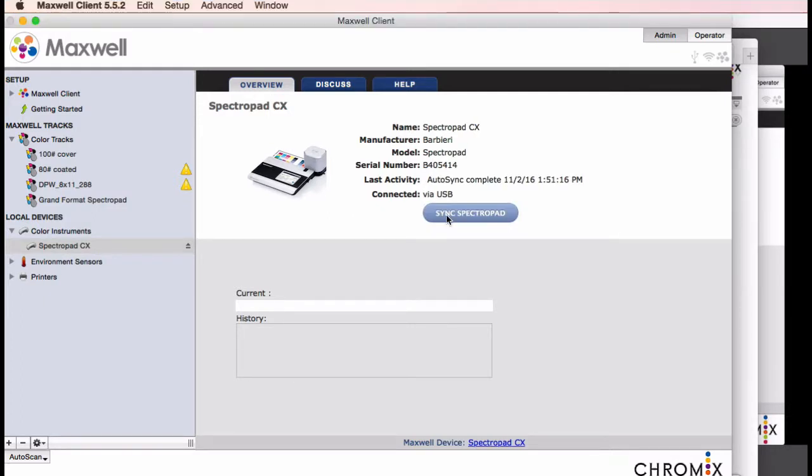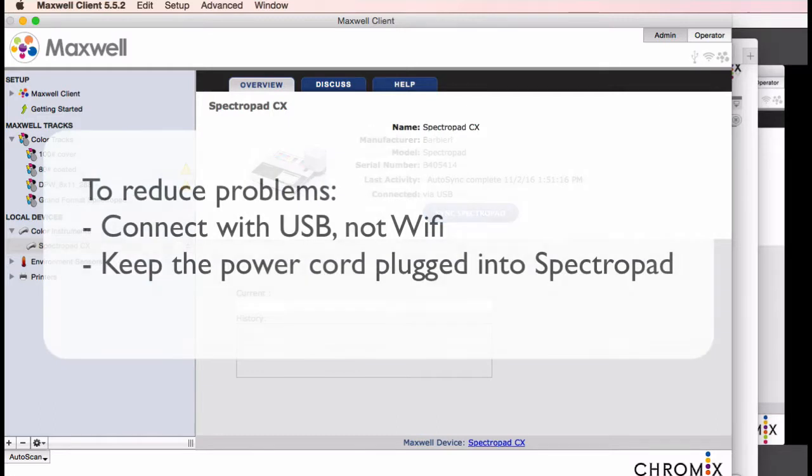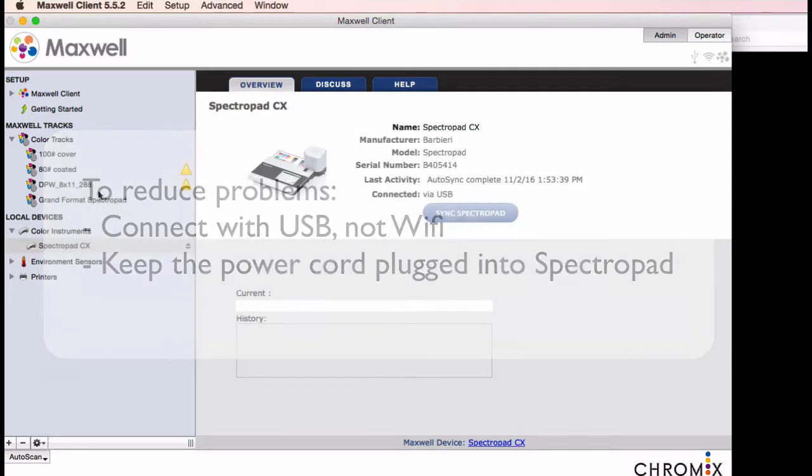Here are some helpful ideas if you run into any trouble. There's a lot at play when using the spectropad, so when troubleshooting, try minimizing the variables, as we say. Connect with USB and not with Wi-Fi. Make sure the spectropad is fully charged, and also keep the power cord plugged in if you're trying to isolate problems.